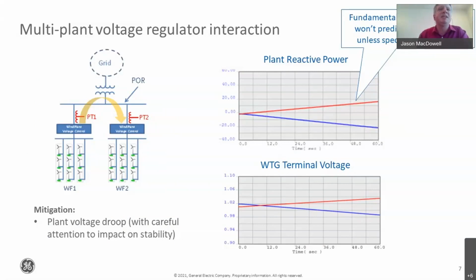One of the issues is plant level regulator coordination, where you have multiple plants together that will interact due to slight errors in PT measurement that will cause VARs to circulate from one plant to the other. You might experience circulating VARs to the point where you hit the limit and have no VARs left to respond to system conditions when you have a grid event.